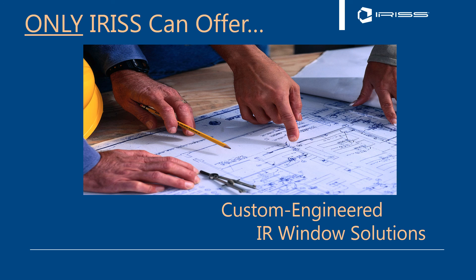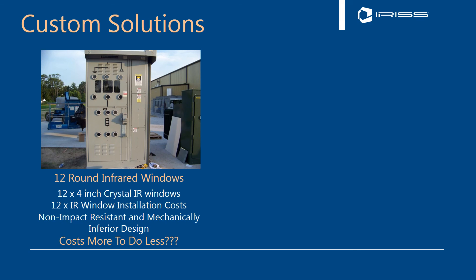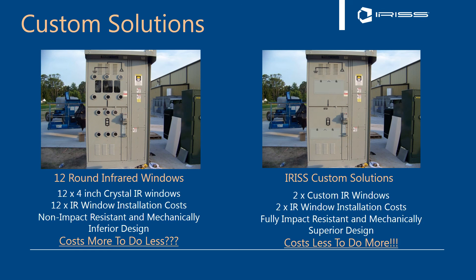Only IRISS offers custom engineering solutions. One of the things we say is: why should you try and fit an infrared window when we can make infrared windows fit you? Looking at a specific example: here we have 12 four-inch round windows at an average cost of $400–$500 each, across 12 installations — non-impact-resistant, mechanically inferior design, costing much more to do less. Our approach is a custom CAP CT series window that goes over the existing Lexan. We remove the Lexan, put the CAP CT series over that — you can still do lockout/tagout, plus do your ultraviolet and infrared inspections through the same window. The example below is a standard CAP CT24.